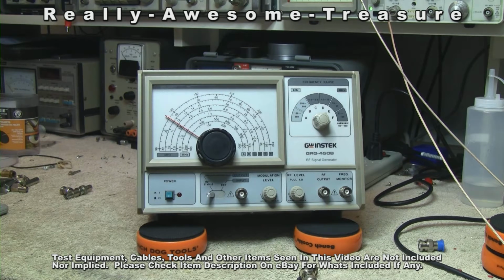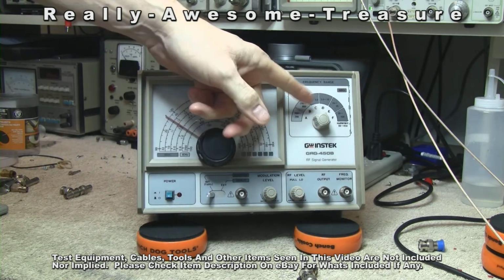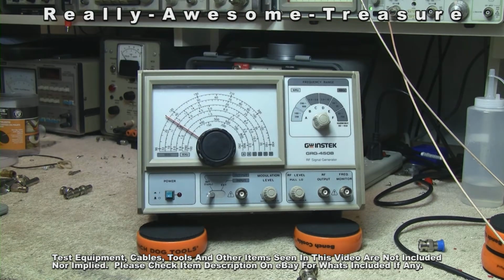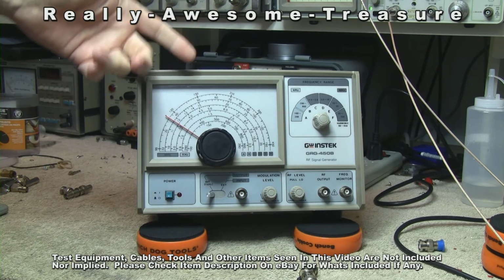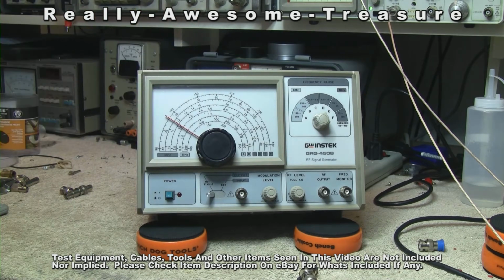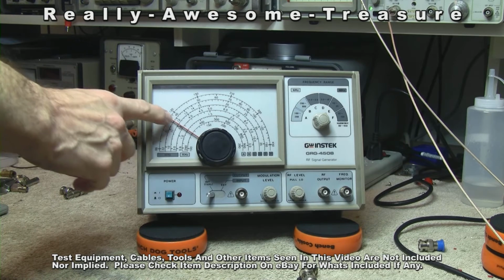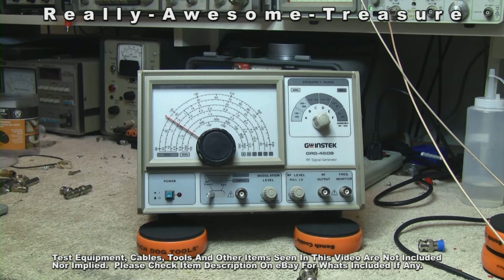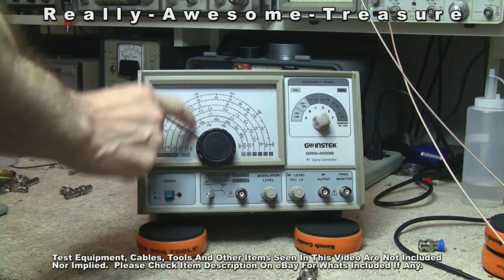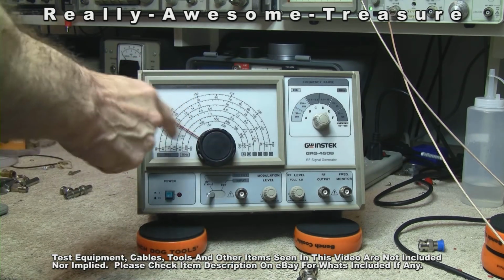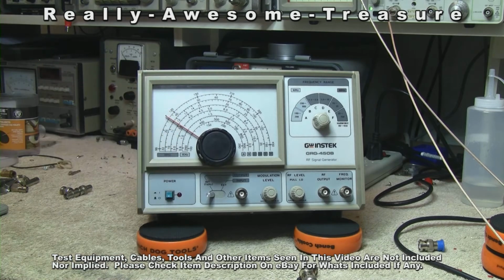As far as internal calibrations are concerned, there's really nothing that you, the tech, can do. On the back side of this control, there are coils. Per the service manual, if you heat up the wax and adjust those coils, that will get you on frequency. But honestly, even though it's not 100% on frequency, it's really doggone close. And if you use a frequency counter, you really don't need to have this exact. This is just going to be a reference point for your eyeballs. Your frequency counter is what's going to tell you where you are.